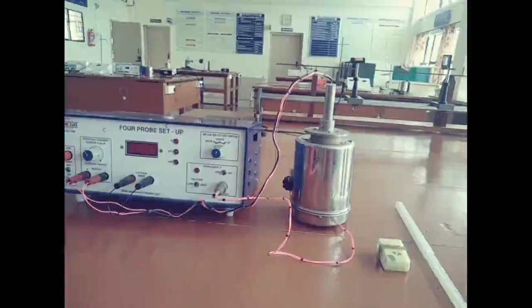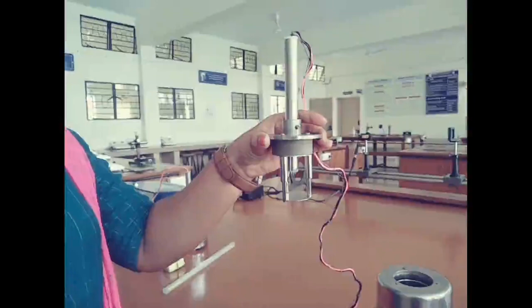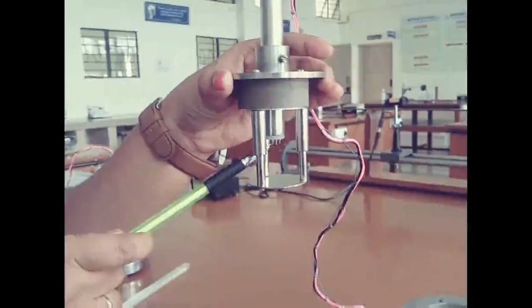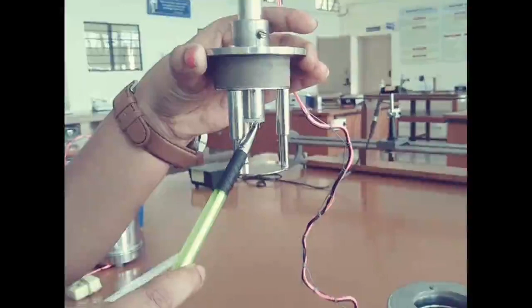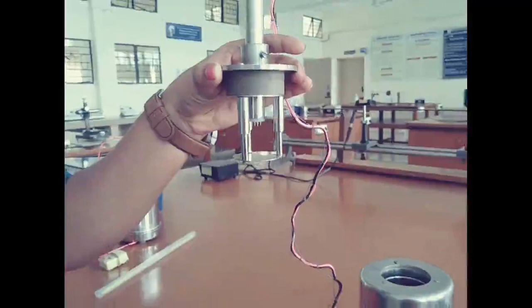arrangement. Now, in order to explain the 4-probe arrangement, I am bringing the demo piece. This is a 4-probe arrangement. It has 4 individually spring-loaded probes. They are collinear and equally spaced. The distance between the probes is 2 mm. This 4-probe is mounted with a Teflon bush and Teflon spacer that help for good electrical insulation between the probes and also help to keep the probes at equal distance.